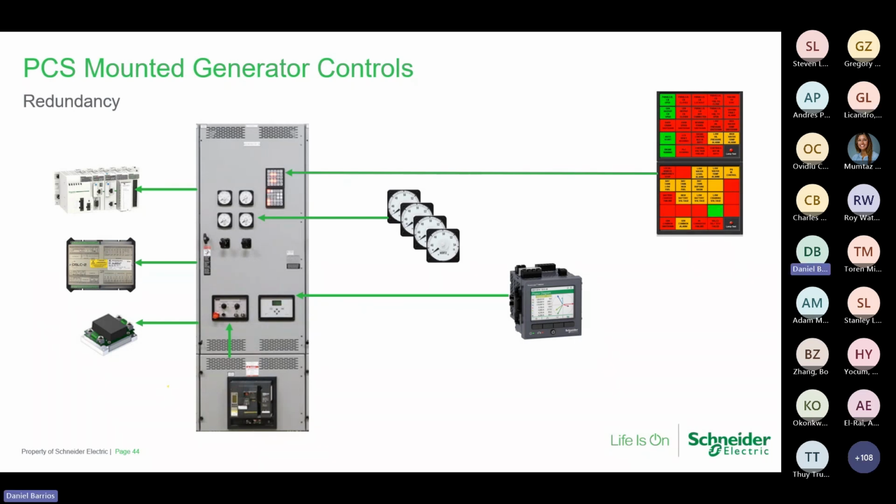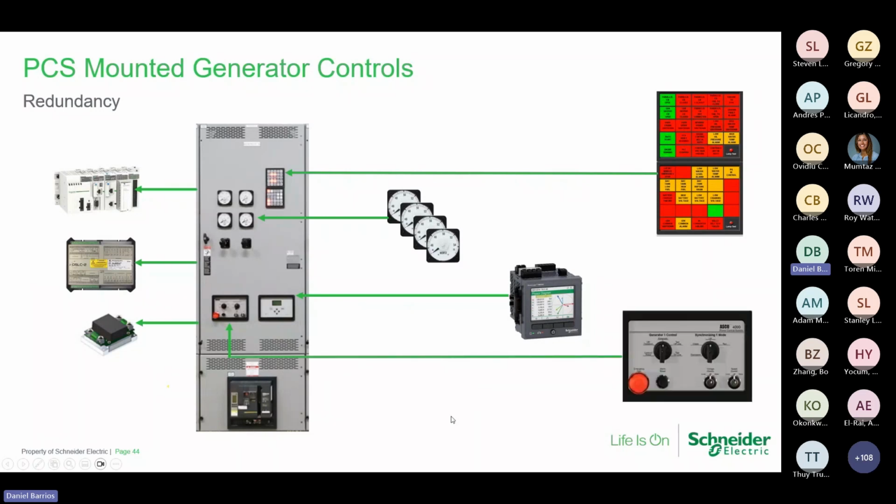Okay. What we have down here now is the controller that connects to the DSLC-2, the digital synchronizer, and that can be a deep dive in itself. But basically on the left side, you can set that D-Slick up and perform functions that will test it to be sure that it will take the generator into synchronization. It will lock it in, but not necessarily close the breaker.